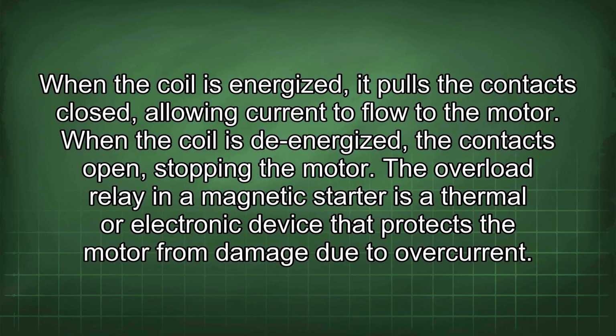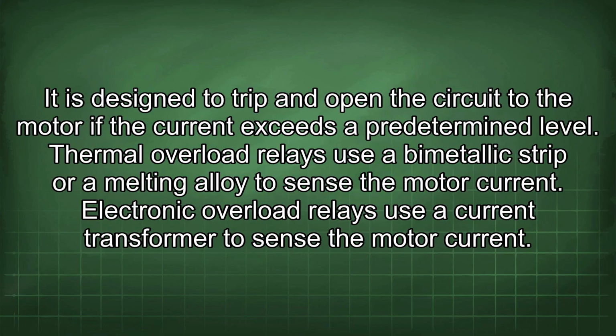The overload relay in a magnetic starter is a thermal or electronic device that protects the motor from damage due to overcurrent. It is designed to trip and open the circuit to the motor if the current exceeds a predetermined level. Thermal overload relays use a bimetallic strip or a melting alloy to sense the motor current.